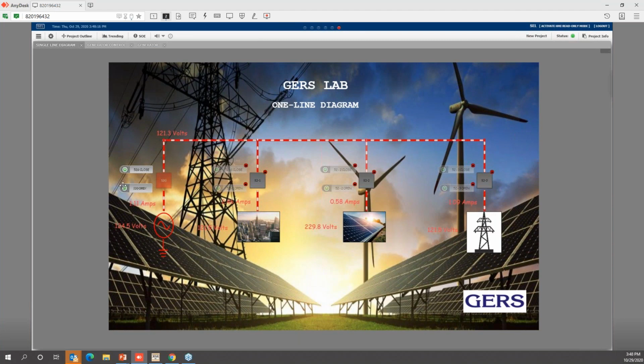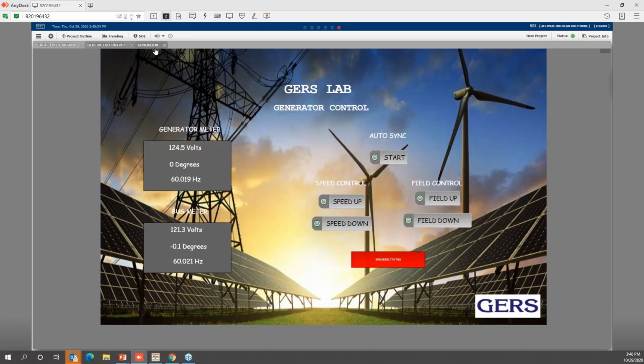What we can do here is open or close the circuit breaker, but it's not easy to close the circuit breaker if the synchronous machine is operating in island mode. Why? We first need synchronization of the system, which has been implemented in the auto-synchronization, where the relays will increase or reduce the excitation and the RPMs to keep the frequency.